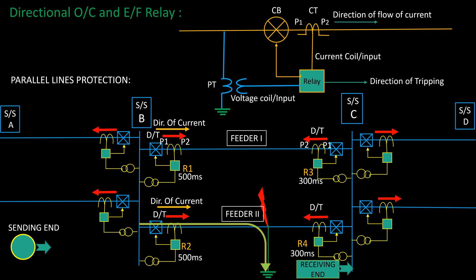On the other hand, a part of fault current flows through circuit 1 via bus and rest part of circuit 2 reaches at fault point in reverse direction. This fault current faces relay R3 in reverse direction and does not issue tripping of circuit breaker against the set relay R3.